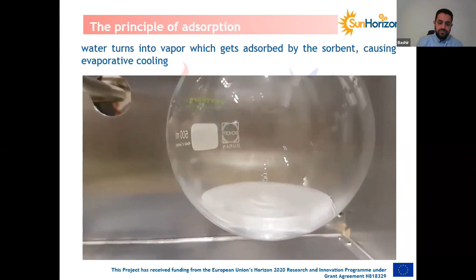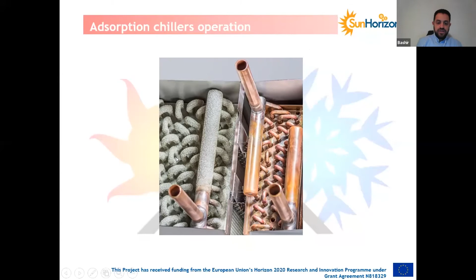In our chillers, we have heat exchangers coated with this sorbent material—in this case, silica gel on the left side heat exchanger. Our machines consist of modules, each containing two heat exchangers: one coated with the sorbent material, and the other functioning as an evaporator or condenser. As with the demonstrator I showed, water evaporates and is attracted to the adsorber, creating the chilling effect.